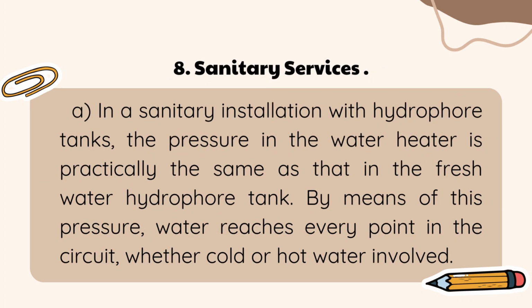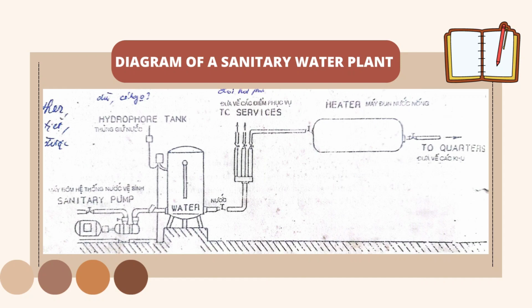8. Sanitary services. A. In a sanitary installation with hydrophore tanks, the pressure in the water heater is practically the same as that in the freshwater hydrophore tank. By means of this pressure, water reaches every point in the circuit, whether cold or hot water is involved. Diagram of a sanitary water plant.